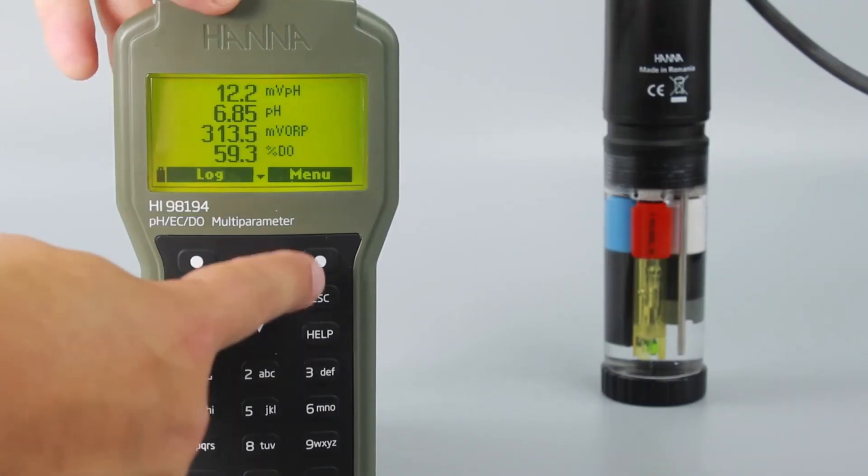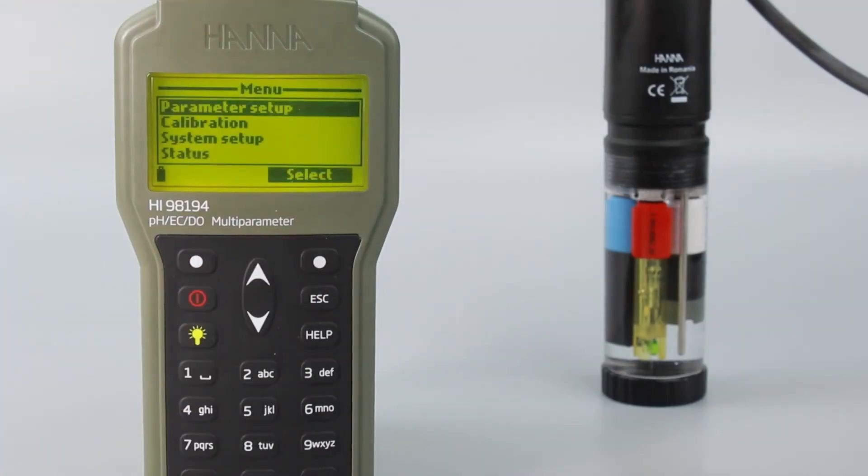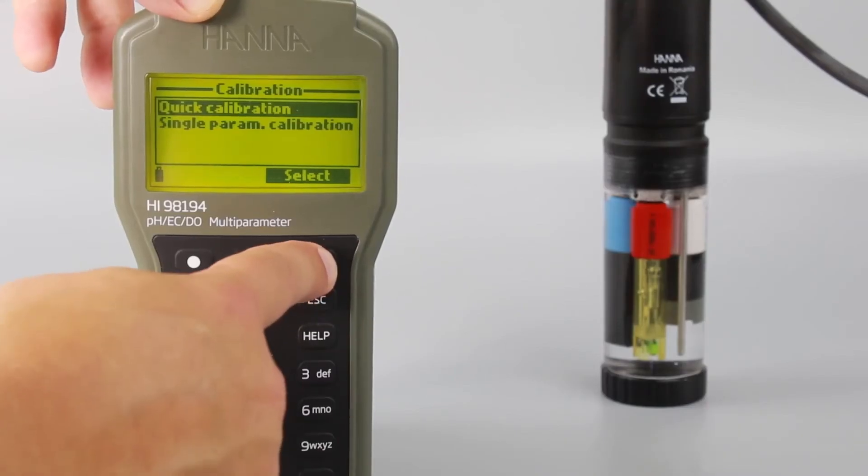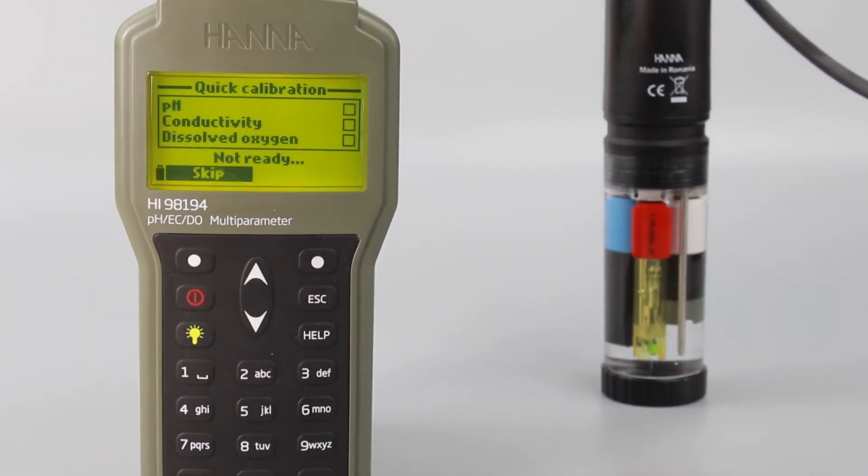From the meter, press Menu and then Calibration. From there, press Quick Calibration and follow the prompts. You'll calibrate for each sensor in stages. If you want to skip calibration on a specific sensor, just press Skip.